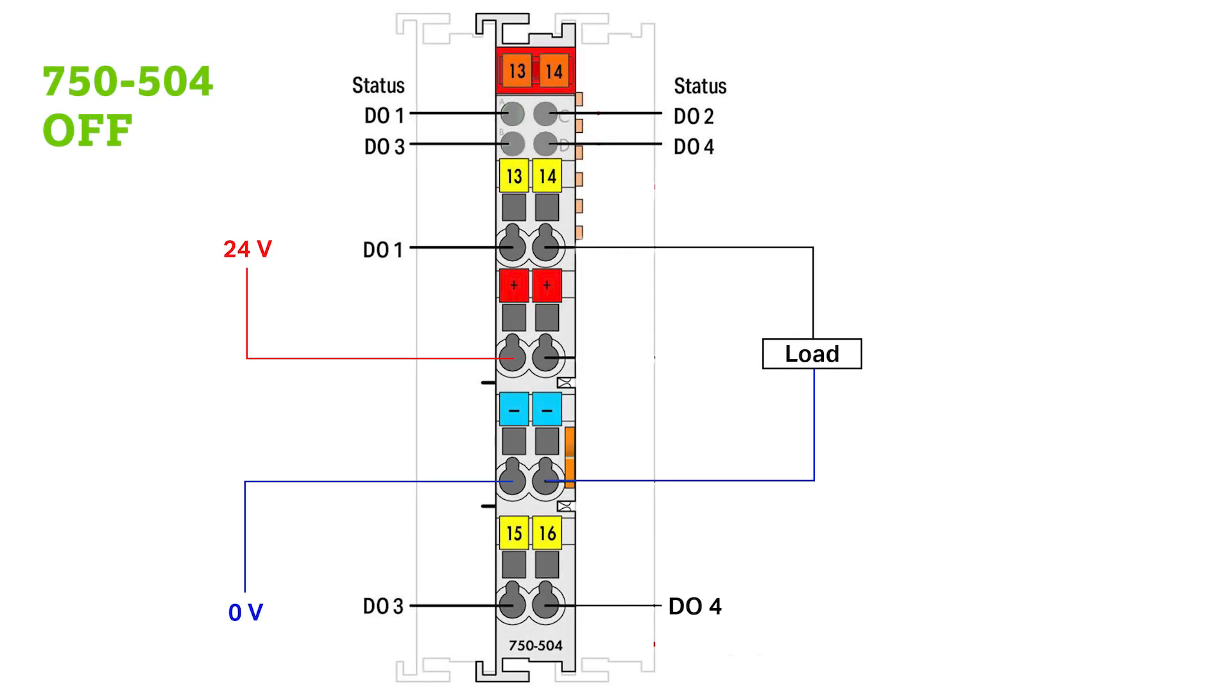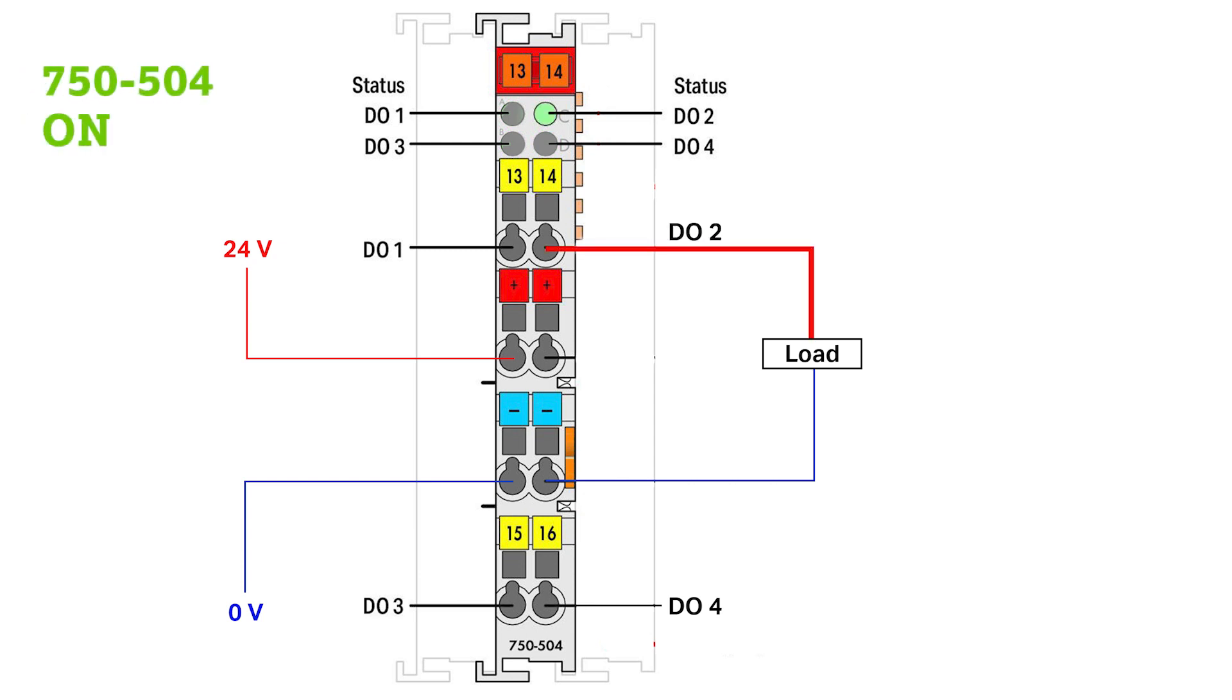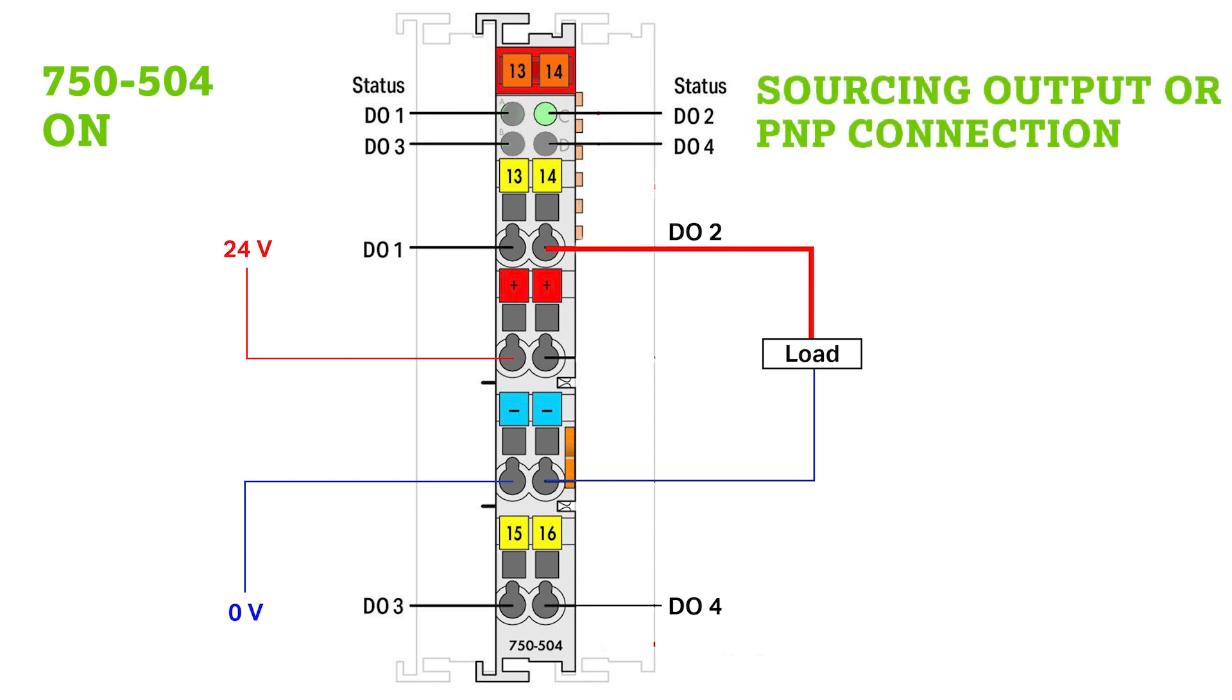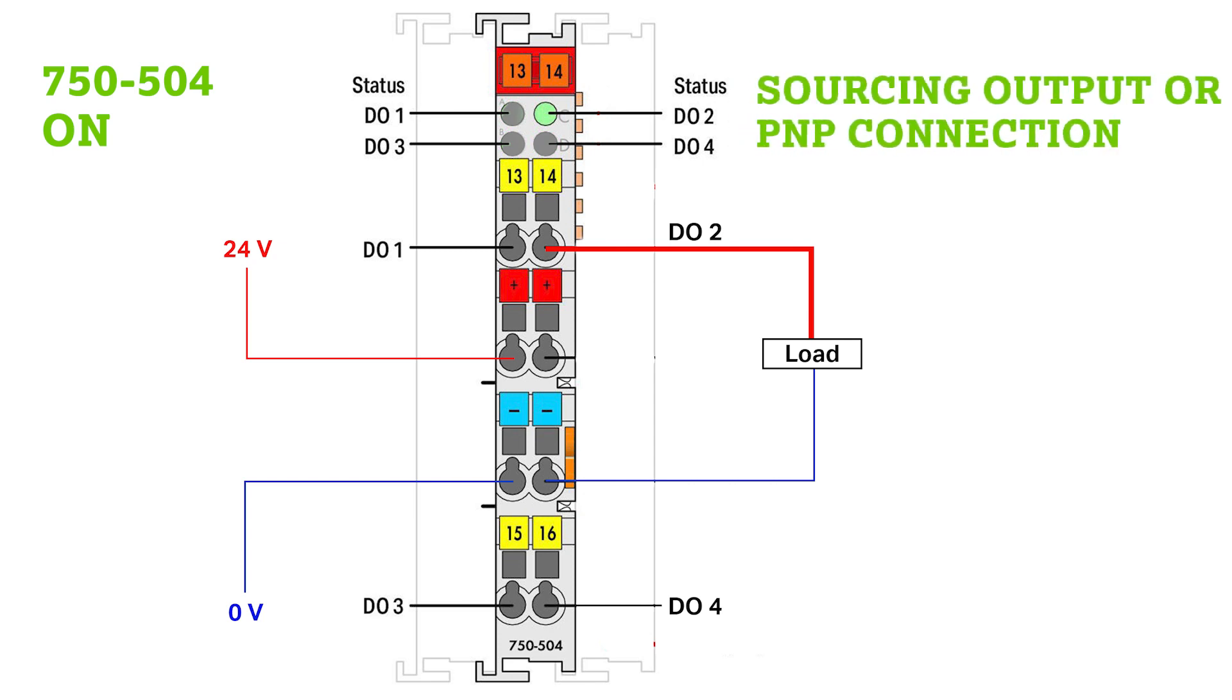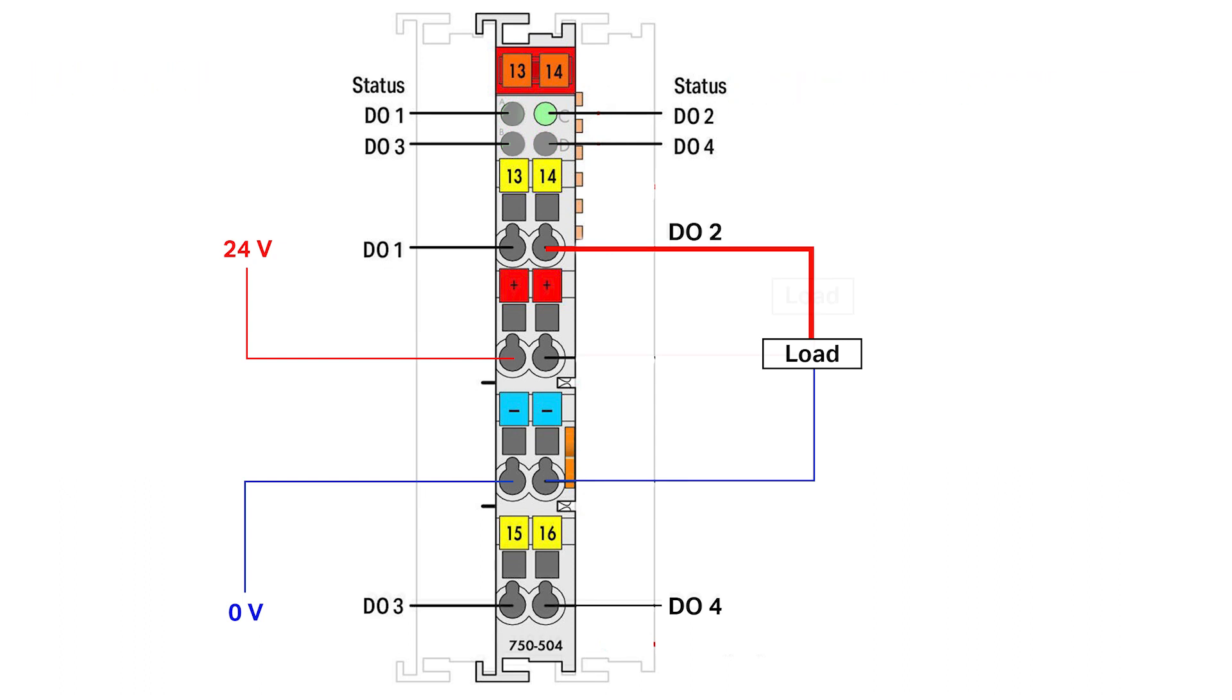Let's look at digital output modules first. WAGO's high side switching output module, the 750-504 for example, supplies and switches the 24V supply voltage as the output of the module going to your load. This is also referred to as a sourcing output or a PNP connection.